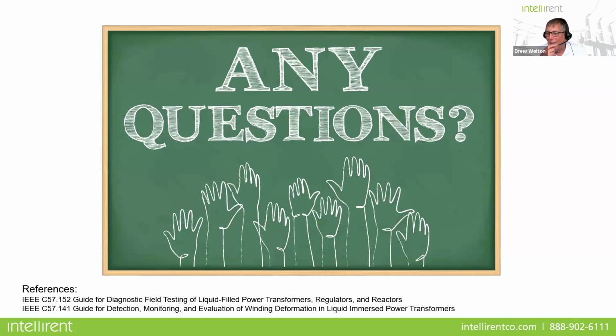She brings up a good point. Yes, the transformer manufacturers, before they sell the transformer and ship it, do basic testing on it, and they provide those test results to the owner as a starting point. Sweep frequency response analysis is the one you want to specify to have done before it ships, because it's going to look for any mechanical deformation during the shipping process. I think it doesn't stop at the factory acceptance test. It stops with proper commissioning.